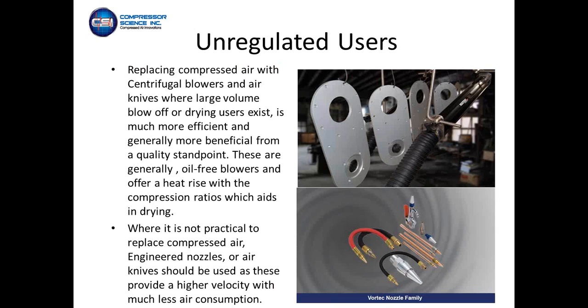Replacing compressed air, and this is where we get into looking at unregulated users and how you're using compressed air at the point of use, because I've gone in a lot of plants where it is not practical to replace compressed air. And although it seems to be a waste and whatnot, you're talking about running dedicated lines, putting in blowers where there's no power, running blower lines and air knives to places where it's really not feasible to fit it into the process.